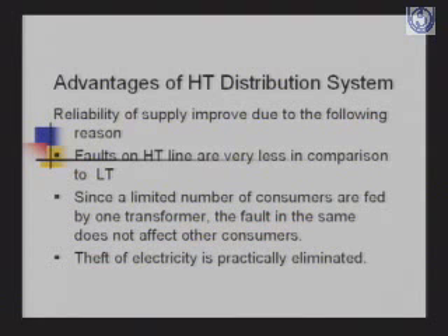Theft of electricity is practically eliminated in such systems because of two reasons. One is that you don't tap an 11 kV line. Secondly, because there are only 3 to 4 customers on that transformer, the customers tend to see that the other customer does not steal electricity. If the transformer is overloaded and destroyed, then only those 3 or 4 customers will be affected. So they try to ensure that your neighboring customer does not steal energy and overload the system.